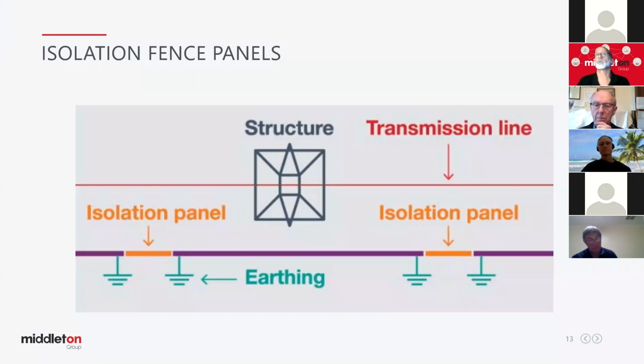Your second part there, I would imagine these high voltage structures have already got one or two overhead earth wires running along them. However, if let's say they're 66 and they haven't got an earth wire there, putting an overhead earth wire in will be a great benefit to reduce the EPR, because now your current that's faulted from a phase to structure has a few different paths. It not only wants to go into the earth grid at the bottom of the structure, it can now go along what we call an auxiliary path along the overhead earth conductor into the structures either side that can help dissipate that fault current, and the ones to the side of those and side of those, effectively all the way back to the supply substation. So yes, it would be a design input that you would probably use prior to using isolation panels. So it's a good question and a good point.